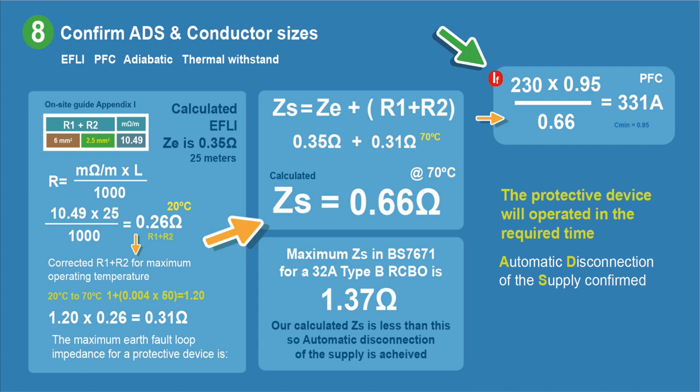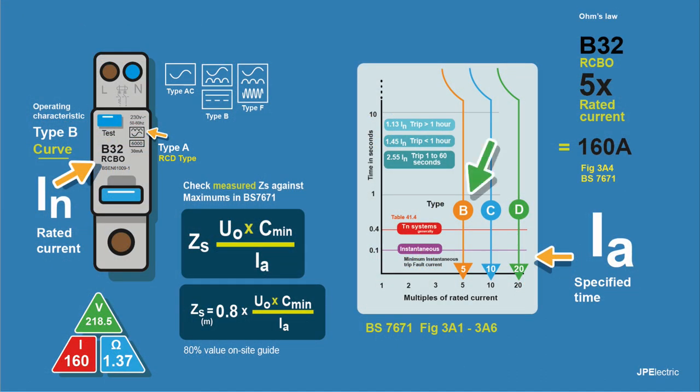We need to calculate the prospective fault current to make sure the protective device will operate within the required time. The formula is 230 × 0.95 (the correction factor Cmin for voltage fluctuations) divided by our Zs of 0.66, which gives us a prospective fault current of 331 amps. For a Type B RCBO, instantaneous tripping is at five times the rated current: 5 × 32 = 160 amps. We have a prospective fault current of 331 amps, so automatic disconnection of the supply is confirmed.